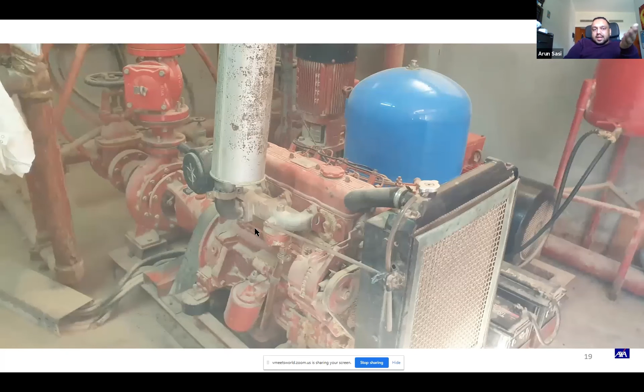This is one of the older fire pumps that I've seen in one of the sites. These are the times before the FM approved listed pumps came into the picture. So you can see that it doesn't have the information. You will not have a speedometer. You will not have an odometer. None of those systems are in place. You will see that the diesel container doesn't have spill protection, and it uses a rubber tubing which goes over the electric motor as well as the batteries. The risk here is quite high. Now, in this particular case, the pumps were off. They were not functional, and they have not been maintained in quite a long time.